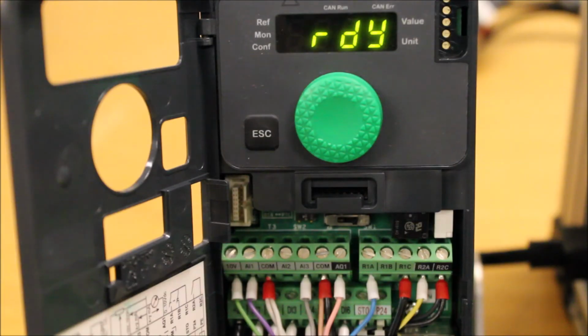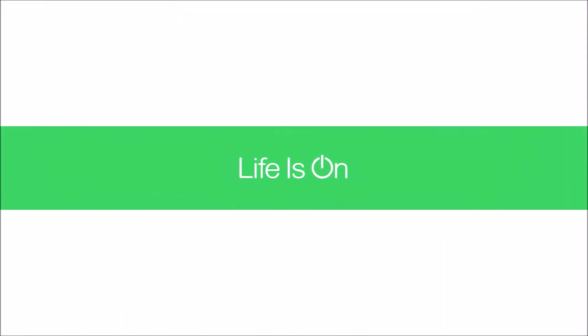Now keep in mind that you can program the presets as network commanded functions as well, so you can assign a particular bit to be a preset as well. But this particular video only shows you the one where you assign a terminal, DI3 and DI4 as an example, for a preset speed functionality on the ATV 320 drive.